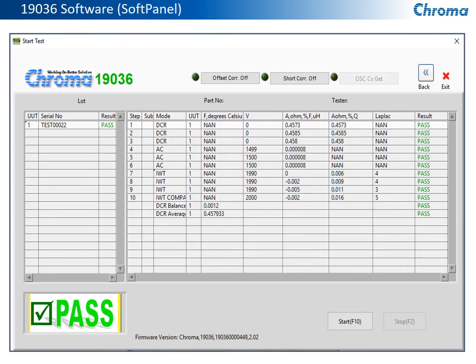The actual data that is recorded will be displayed in the software like you see it here. And this gives you, here you can see we ran 10 individual steps within this single program. And with those 10 steps, we were able to measure DC resistance as well as a DC resistance balance and average test. We also did the AC high pot test and an impulse winding test on all three windings, as well as a impulse winding test comparison. So we were able to do all those tests quickly, efficiently, record all the data, and give you an indication of pass and fail, all done within this software with our 19036.